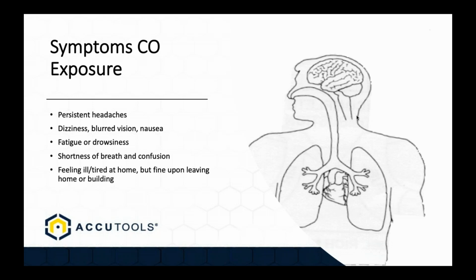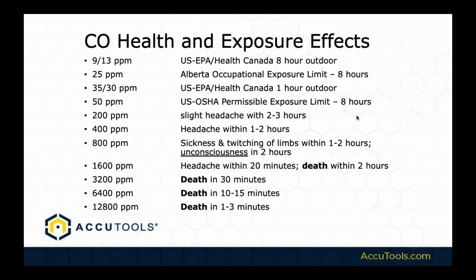And really, a combustion analyzer should be used year round for this. We talk about these sensors, they're chemical sensors. They're wearing out whether you use them or not. And you should be testing for CO annually, year round, summer, winter. You still have combustion appliances, hot water tanks, dryers burning in the house. You want to test for that CO year round, and it should be part of your regular inspection.